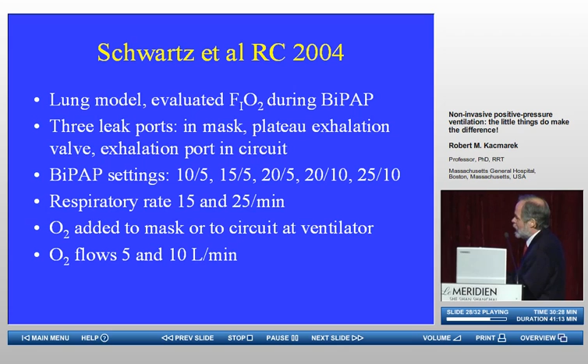So we used a lung model. We had 3 different leak ports, one in the mask. We used the plateau exhalation valve, and then the exhalation port in the circuit itself. Numerous settings of the ventilator, 2 respiratory rates, O2 added in 2 different positions, in the mask and in the circuit, and then 2 different liter flows of O2. And this is what the setup essentially looked like.